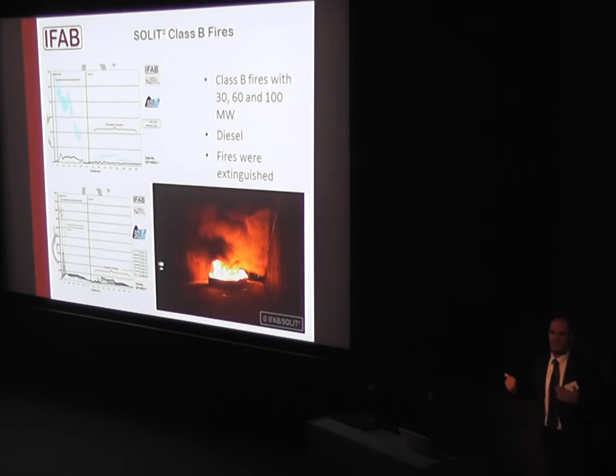Furthermore, you have to know this method is quite sensitive to any changes in the system. So if you activate a fire suppression system, then forget your measurements. Heat release measurements are not right anymore, or at least not right during this period, let's say 30 seconds to 1 minute around this action. They are measuring nonsense, because you're mixing up everything, you're changing the airspeed and everything, so that's not right.